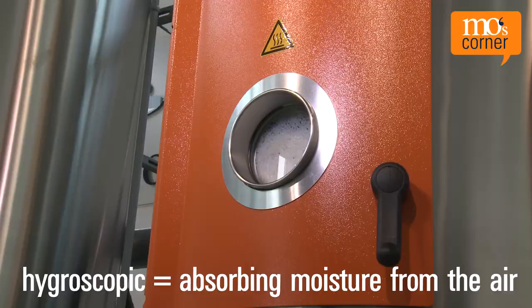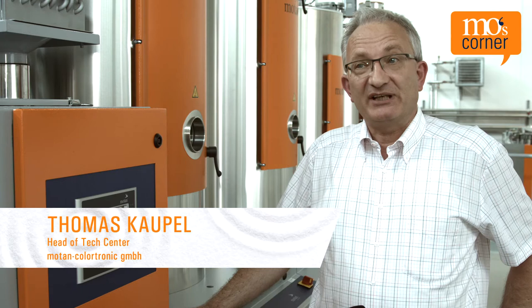Dry air dryers are usually used when a hygroscopic material has to be dried and a specific dew point is required. A drying system generally consists of two functional units: one unit which generates the actual process air — the dry air — and one which provides the airflow onto the actual drying bin.